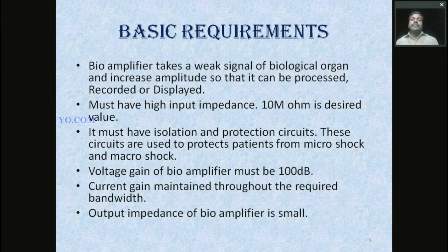What is isolation? The human is connected with the bioamplifier through the electrode and lead wires. The other end of the bioamplifier is connected with the display unit or some other high voltage applications. So the isolation between the human and high voltage is very important.